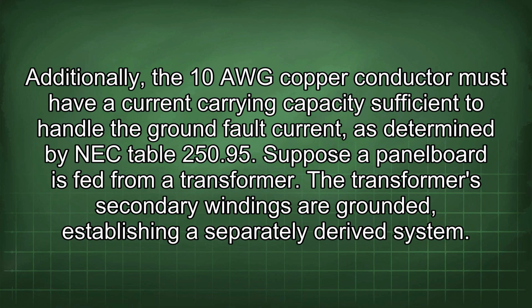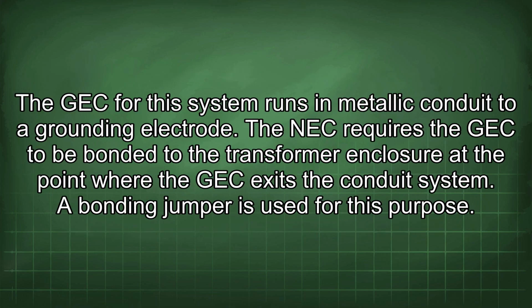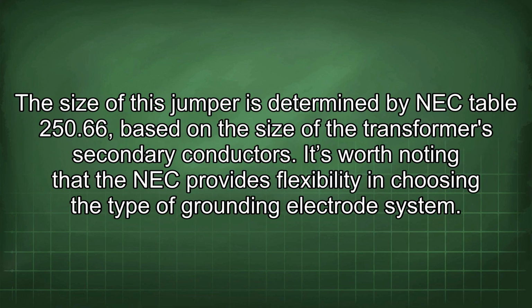Suppose a panel board is fed from a transformer. The transformer's secondary windings are grounded, establishing a separately derived system. The GEC for this system runs in metallic conduit to a grounding electrode. The NEC requires the GEC to be bonded to the transformer enclosure at the point where the GEC exits the conduit system. A bonding jumper is used for this purpose. The size of this jumper is determined by NEC Table 250.66, based on the size of the transformer's secondary conductors.